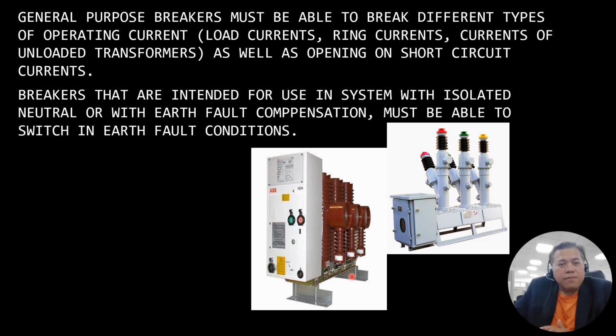If I recall, way back 5 or 7 years ago, one of the technicians asked us during our commissioning activities, when we were energizing our transformer and switchgear, if the earth switch can be transferred. So that's a funny question, right? The earth switch is already connected in our switchgear, so we cannot relocate that one, right?